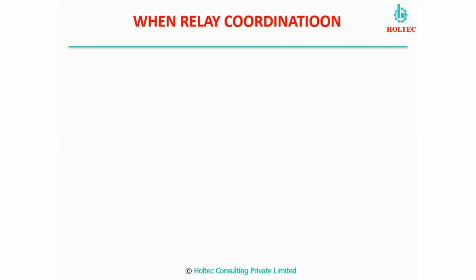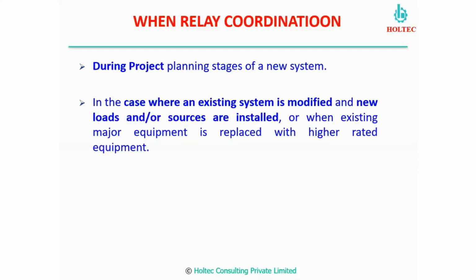So when is this relay coordination to be done? Ideally, when you are in the project stage, you have to have a proper relay coordination. Then, if you are adding or modifying the system, adding any load, adding any source, or changing the rating of any major equipment, there is a need to do the relay coordination again.